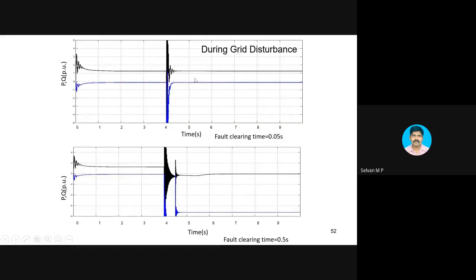Then there is a grid disturbance which is happening at 4th second, and the fault is cleared at 0.05 second. In that, we consider two case studies: 0.05 second fault clearance and 0.5 second fault clearance. If the fault is cleared in 0.05 second, then no problem at all. I am able to supply the same real power, and the reactive power requirement is also very less. The capacitor is sufficient to supply the reactive power.